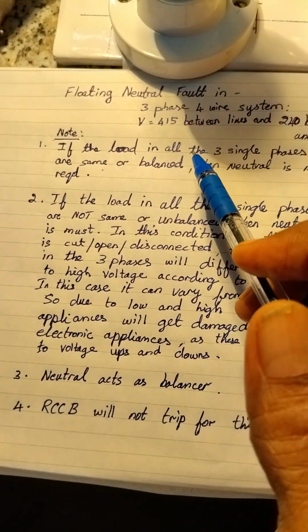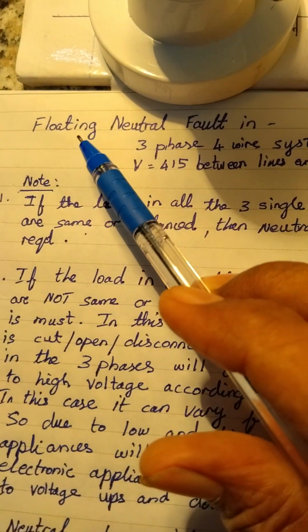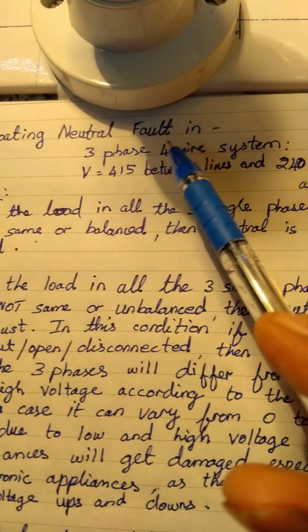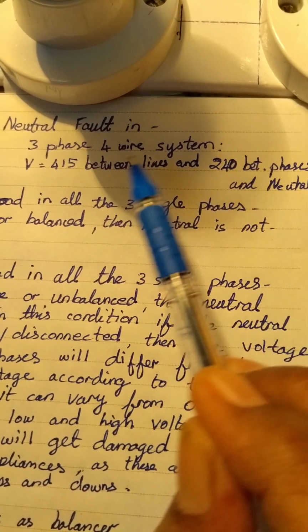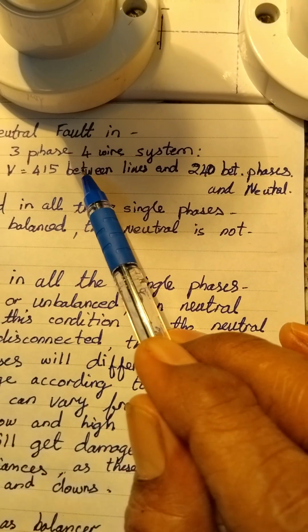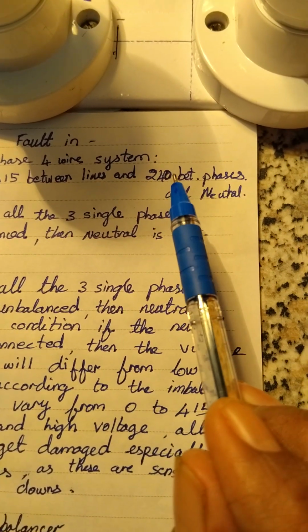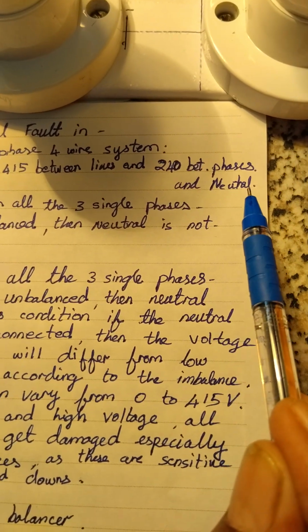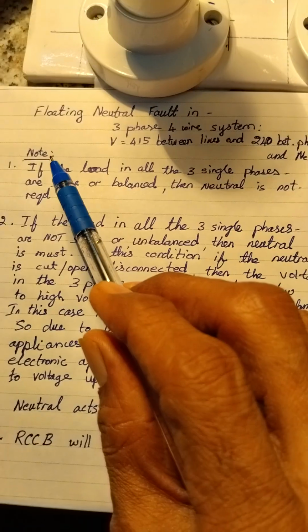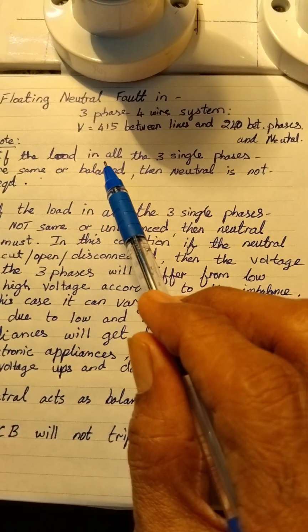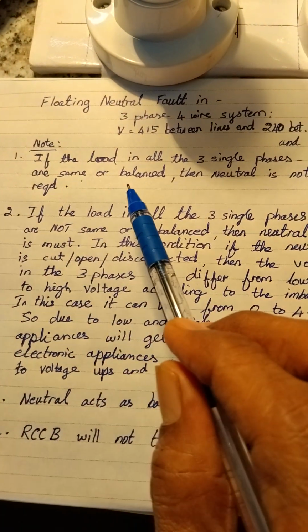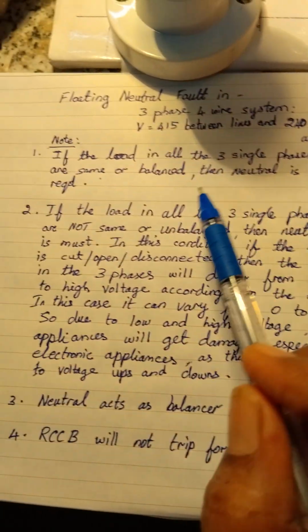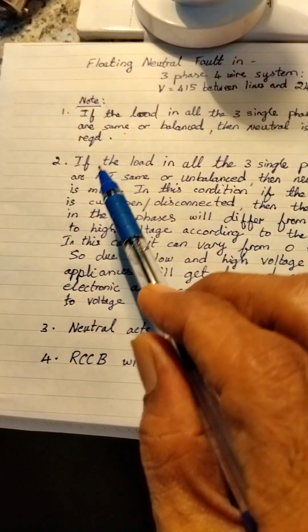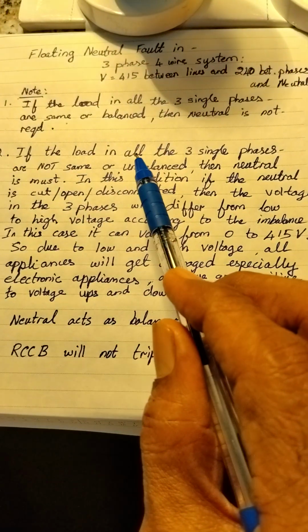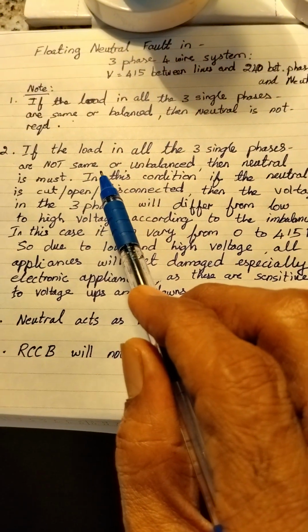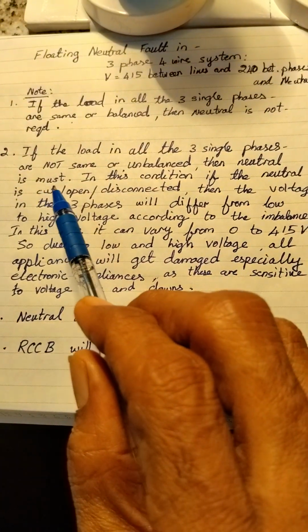Here is the note. The title is Floating Neutral Fault in Three-Phase Four-Wire System. The voltage is 415 volts between lines and 240 between phases and neutral. So we will go into note number 1. If the load in all the three single phases are same or balanced, then neutral is not required. Point 2. If the load in all the three single phases are not same or unbalanced, then neutral is a must.